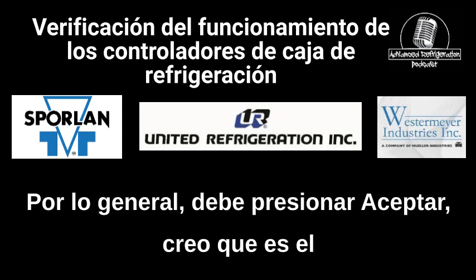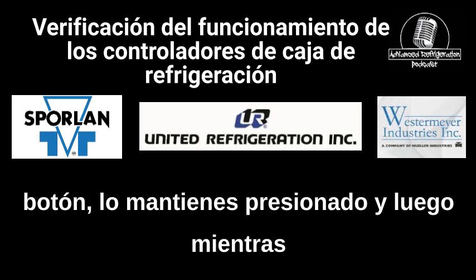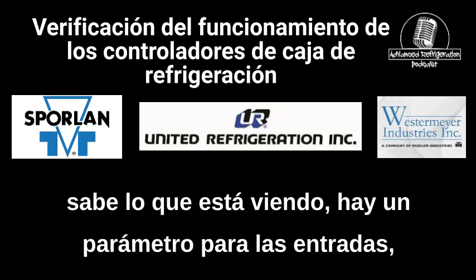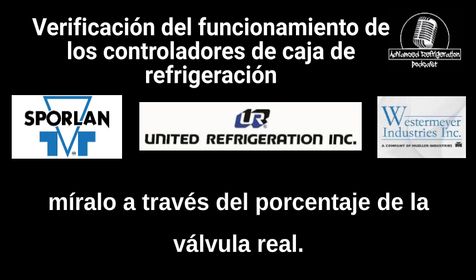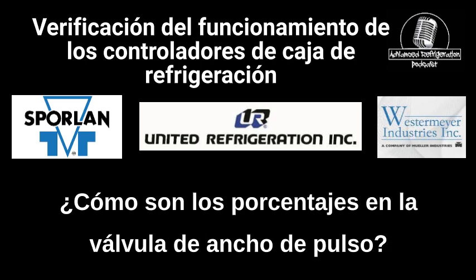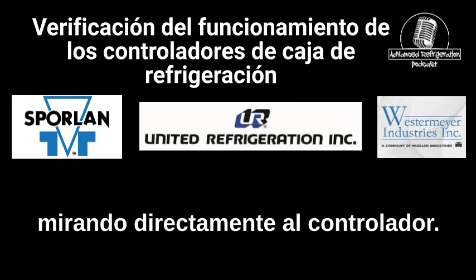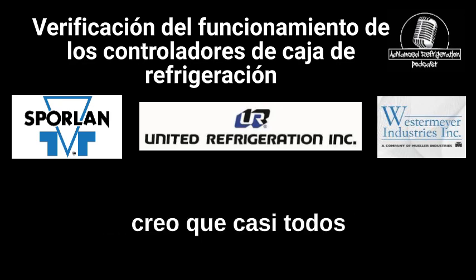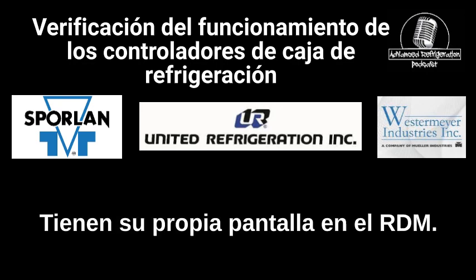Typically, you have to press, I can't pick. Okay, I think it's the enter button, because it's the top left button and the bottom button. You hold it, and as long as you know what you're looking through, there's a parameter for inputs, outputs, and it's been a minute, but you can look through the percentage of the actual valve, like what the percentage is on the pulse width valve. It's fairly easy, and you're looking right at the controller. I think almost all of them actually come with a display. Yeah, they have their own display in the RDM.